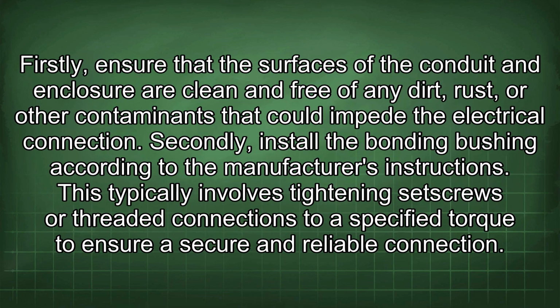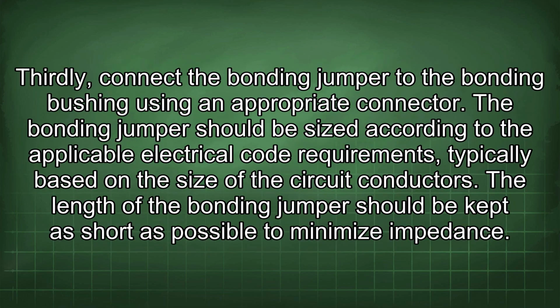Firstly, ensure that the surfaces of the conduit and enclosure are clean and free of any dirt, rust, or other contaminants that could impede the electrical connection. Secondly, install the bonding bushing according to the manufacturer's instructions. This typically involves tightening set screws or threaded connections to a specified torque to ensure a secure and reliable connection. Thirdly, connect the bonding jumper to the bonding bushing using an appropriate connector. The bonding jumper should be sized according to the applicable electrical code requirements, typically based on the size of the circuit conductors. The length of the bonding jumper should be kept as short as possible to minimize impedance.